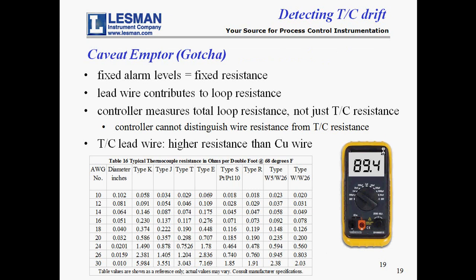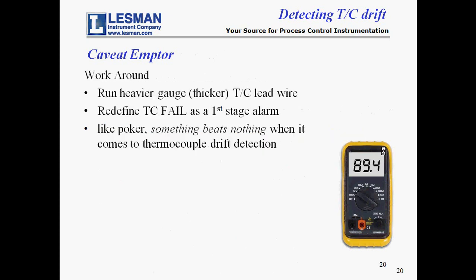There is one limitation you should be aware of: the fixed drift detection levels. Thermocouple lead wire contributes to the total loop resistance. The controller does not know whether the resistance it sees is from lead wire or from a polluted thermocouple junction, or both. Thermocouple inputs with a long run of extension wire can have resistance high enough to appear to be drift, but is really resistance due to the lead wire. There is a workaround. The alarm trip levels are fixed and not adjustable, so you can either use heavier gauge, larger diameter, lower gauge number lead wire, or use the TC FAIL alarm and redefine it as a first-stage alert rather than a second-stage alarm. When it comes to detecting thermocouple drift, it's like poker — something beats nothing.